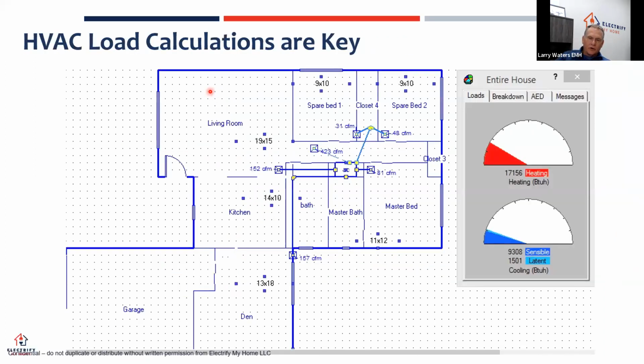But to install inverter heat pumps, you have to find a contractor. If you're an HVAC licensed contractor and solar now, learn to do load calcs. Load calcs are extremely important when we're sizing heat pumps more than ever. Old furnaces have a lot of waste heat. They have a lot of capacity and they heat the house up really quick. People don't notice the inefficiencies in the house when you're blowing hundreds of thousands or thousands of BTUs into the house at one time. So when we install a heat pump, it's going to be a smaller system.